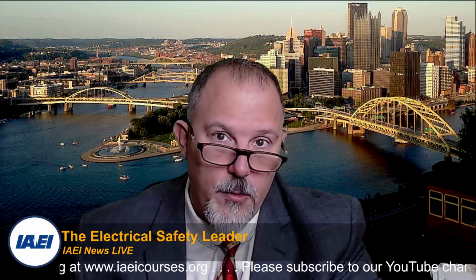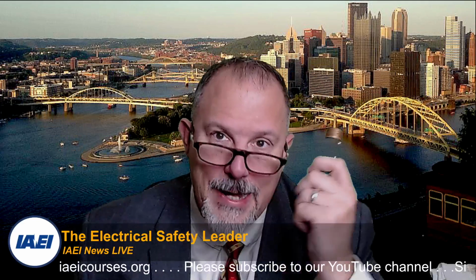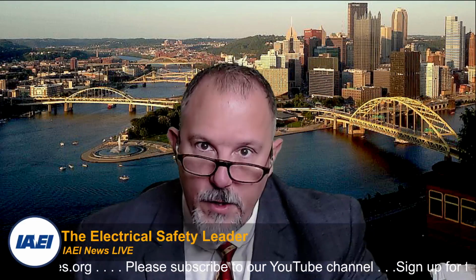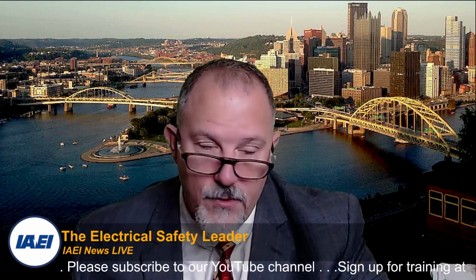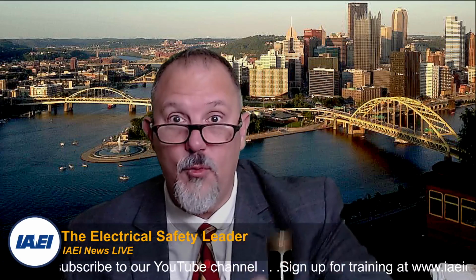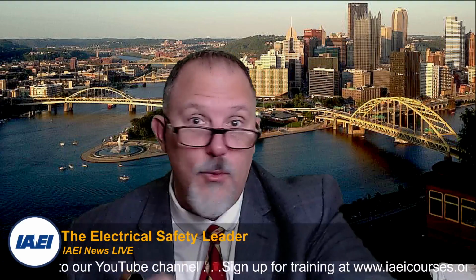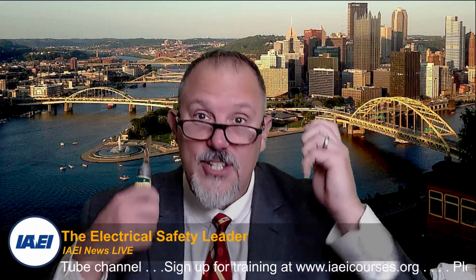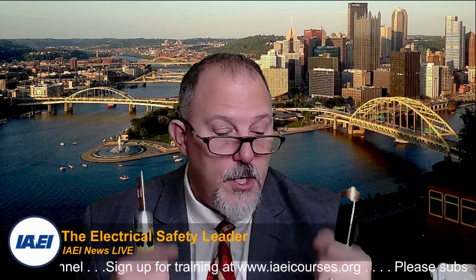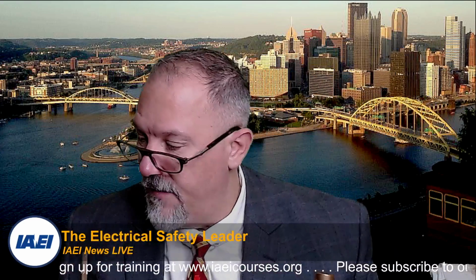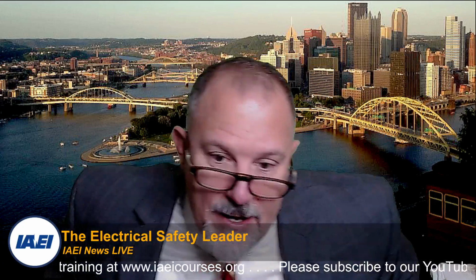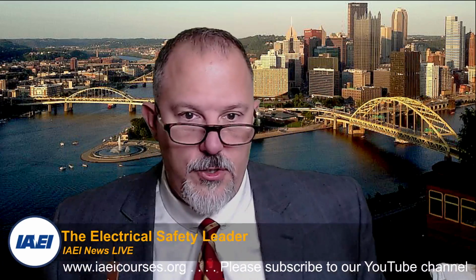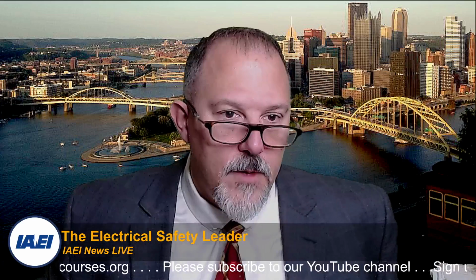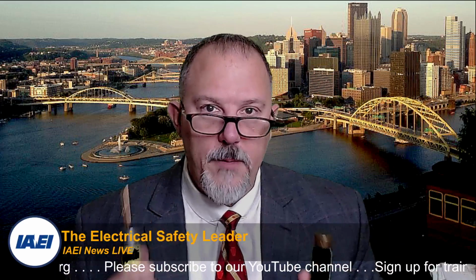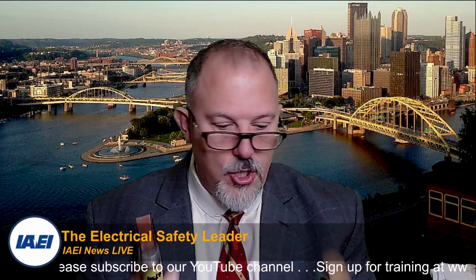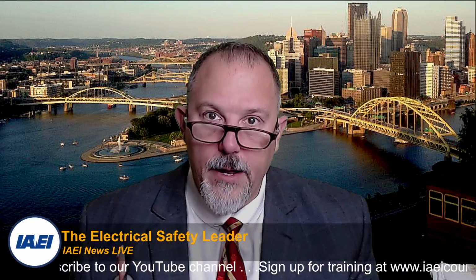Can I apply this on a 480 volt system? Yes. Can I apply this on a 240 volt system? Yes. 230 volt system? Yes. 230, 231, 480, 481, 482, whatever it takes, as long as I don't exceed 600 volts. So from a fuse perspective, I have to admire their attention to safety with regard to helping people ensure they don't misapply the product.